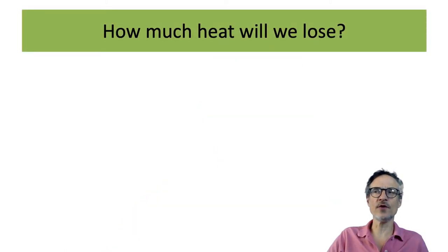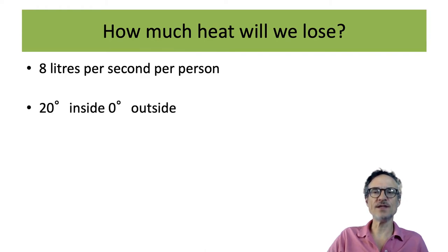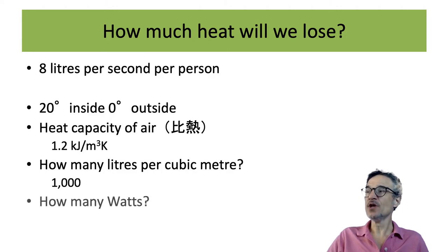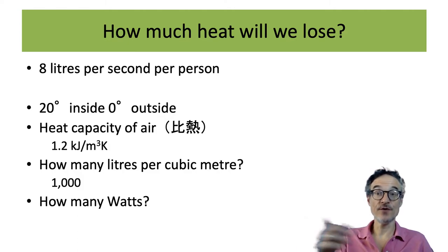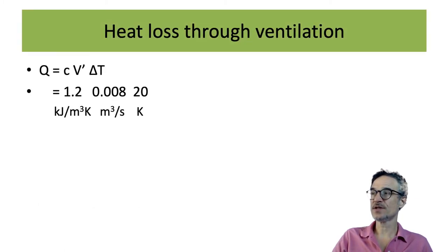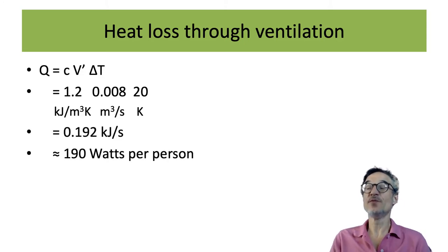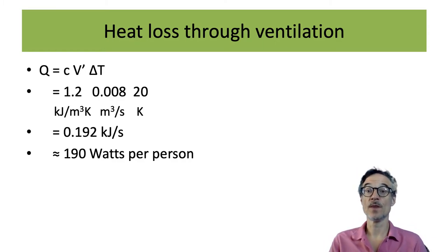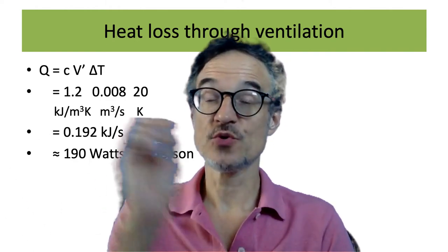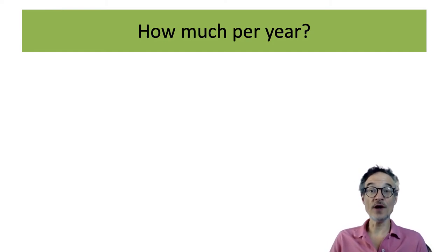We can work this out. If we've got eight litres per second per person, say it's 20 degrees inside and freezing outside, we know how much heat is in the air and how many litres are in a cubic metre, so we can work out how many watts we are losing. If we're ventilating at eight litres per second per person, how many watts are we throwing away in that hot air as colder air comes in? This gives us the extra heat needed per person to make up for the hot air we're throwing away when it's, say, zero degrees outside and 20 degrees inside.